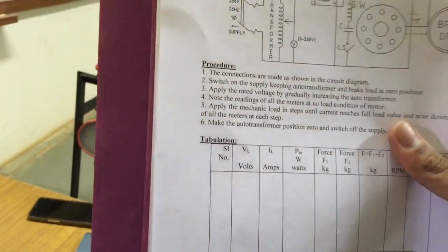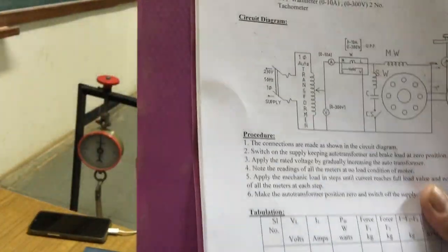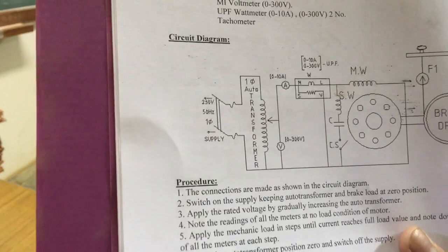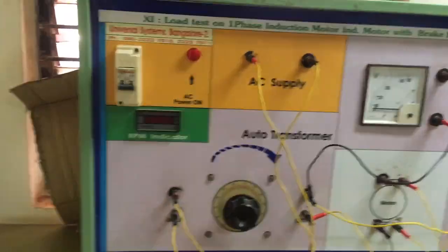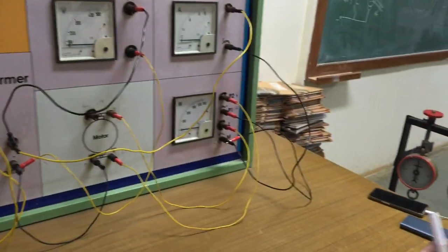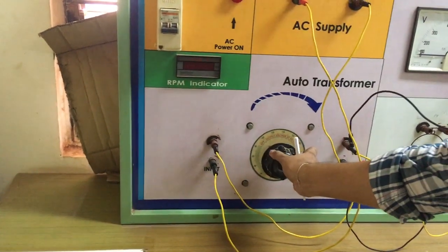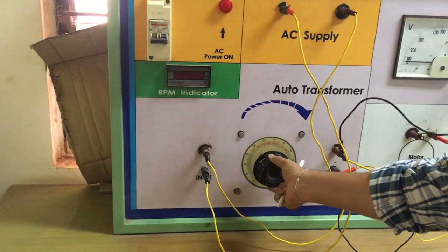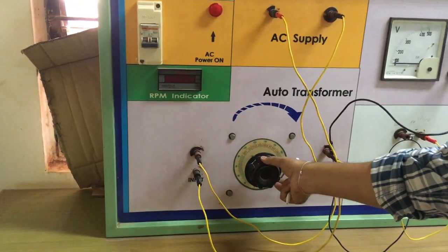Connections are made as per the circuit diagram. We have done the connections. Switch on the supply, keeping the auto transformer and brake at zero position. Before we turn on the supply, we should ensure the load on the motor and the auto transformer position is minimum. If we move it in a clockwise direction, the auto transformer goes on increasing its voltage.